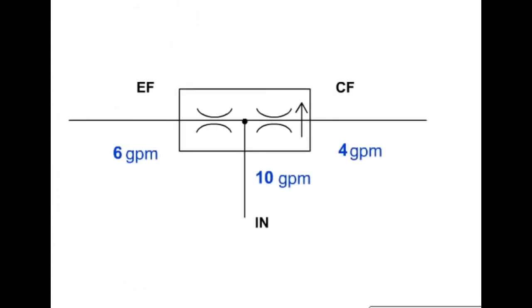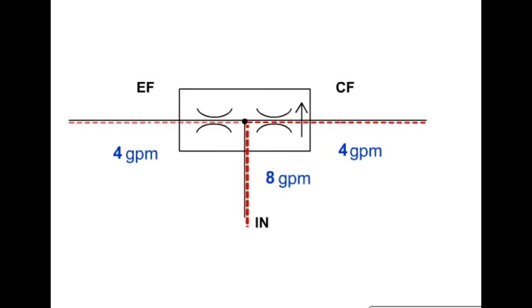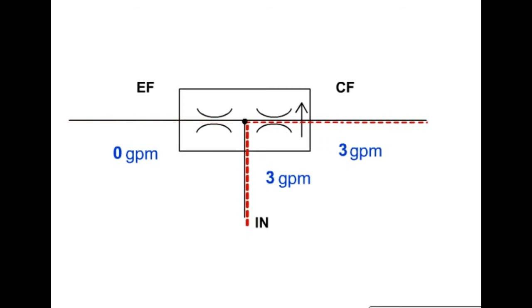The priority or controlled flow port is pressure compensated, but the excess flow port is not. All input flow first goes to meet the required flow of the controlled flow circuit. Flow will remain constant through the controlled flow port as long as it is at least equal to or more than the controlled flow setting. Any extra flow will exit the excess flow port and can be used in another circuit.